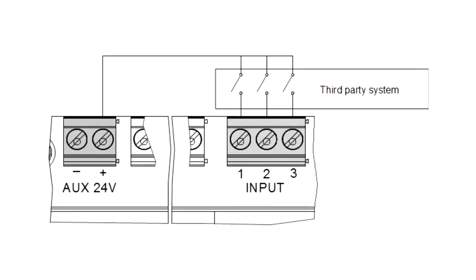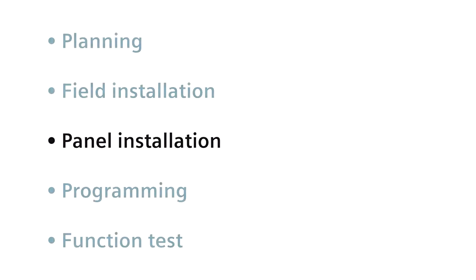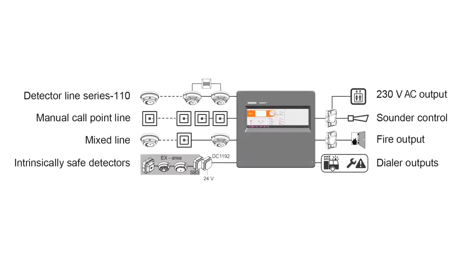The programmable input function allows a third-party system to control the panel. To trigger such a 24 volt DC input signal from the panel, it must be connected via the potential-free contact of the third-party system to the Cerberus fit panel. Panel installation. Before we start with the panel installation, let me present a brief overview of the Cerberus fit system.